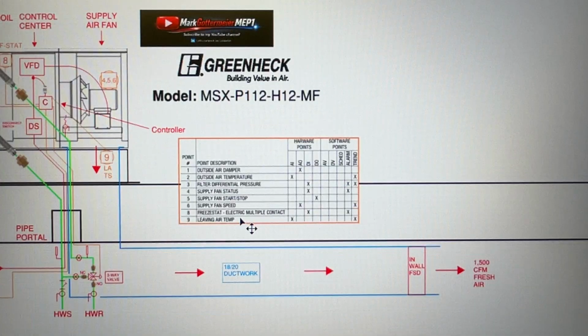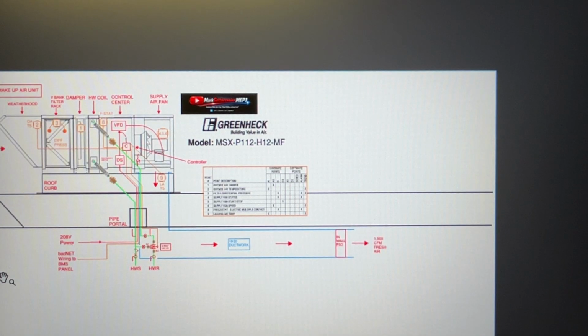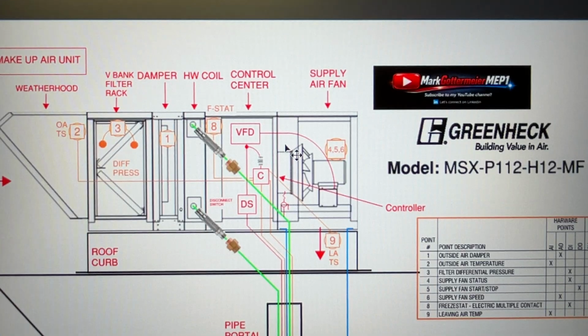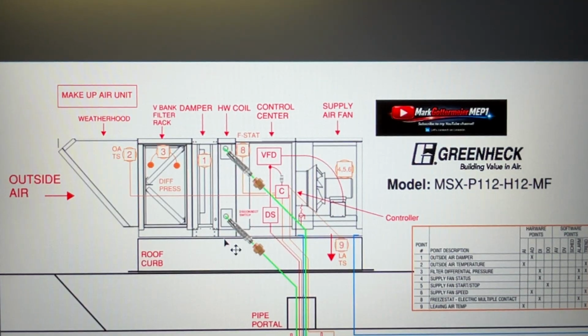So those points I took and put as they relate to the unit itself. So I'll zoom in here. Let me slide over. So our outside air damper, point 1, is here. That damper opens and closes as the controls require. Point 2 is our outside air temperature sensor. So we have a probe out here as that outside air comes in, telling us what the temperature is outside. Our filter differential: we've got this V-bank filter rack, so we're going to have a probe on the inlet side and a probe on the outlet side. That will send what that difference is back to the controller.